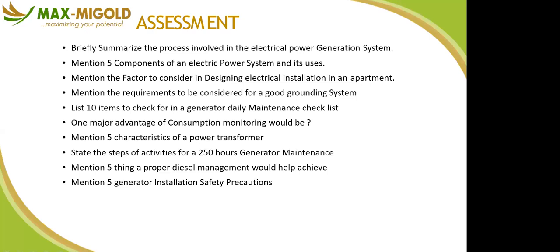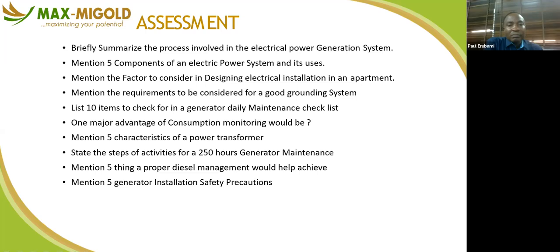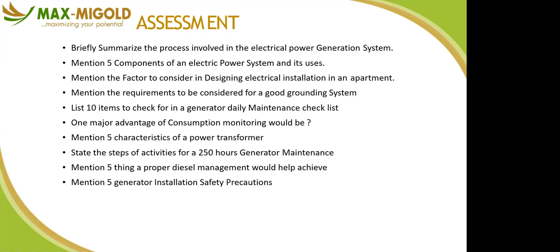Going back to the last question my colleague talked about, when you calculate the load, it is applicable to me. For that particular building, the load calculated was 500 kVA. And then we bought another 300 kVA as a backup. But because the metering system has the diesel meter and we also have the PHCM meter, we found out, because the place started running in May, that people are actually not putting on anything, because now they can see what they are using. So that means both generators are underutilized.